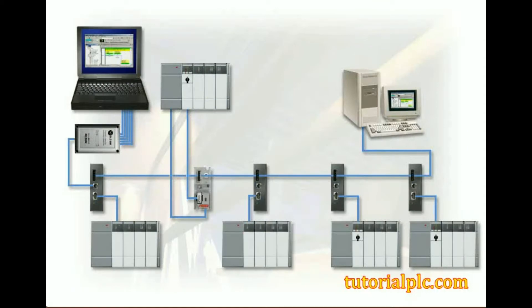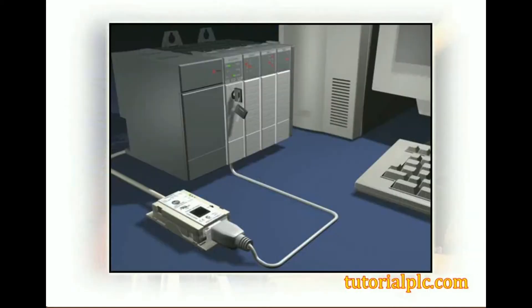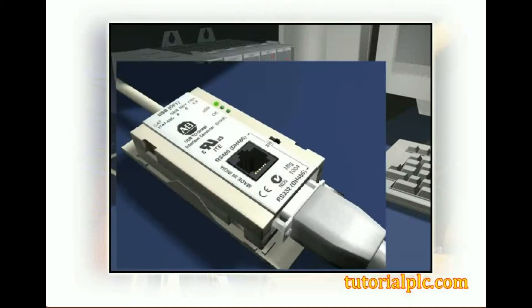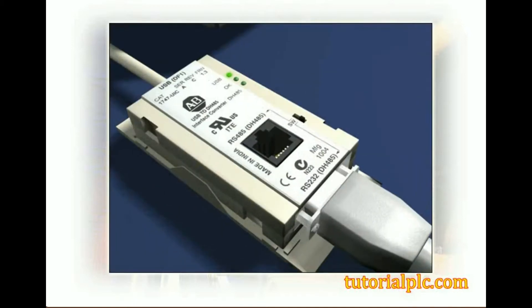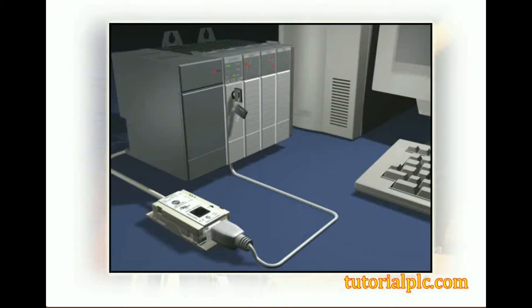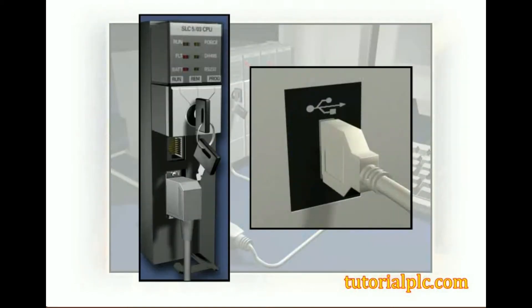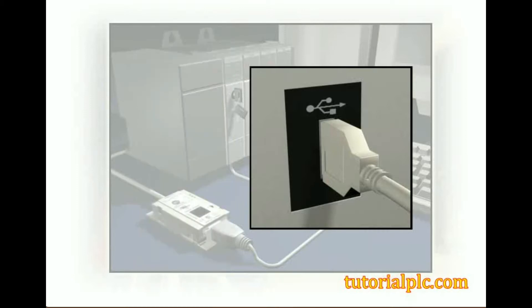Next, let's explore the hardware requirements for communications via a DH-485 network. If we want to connect a computer directly to an SLC 500 processor via a DH-485 connection, we can use an SLC 503 processor and a 1747 UIC module, which is a USB or universal serial bus to DH-485 interface converter. The 1747 UIC module connects to the computer's USB port and to an SLC 503 processor's DH-485 or RS-232 connector. The UIC module receives its power from the computer's USB port.